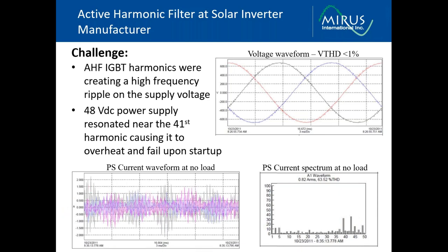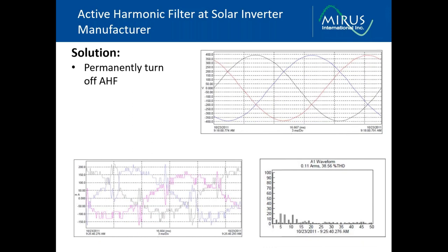And the power supply on the tester, when it was sitting idle, was drawing in very high frequency currents. When I identified this and recognized the effect of the active harmonic filter, I suggested that they shut down the active harmonic filter, and we went back and took some measurements. And as you can see here, with the filter disconnected, the high frequency ripple disappeared.